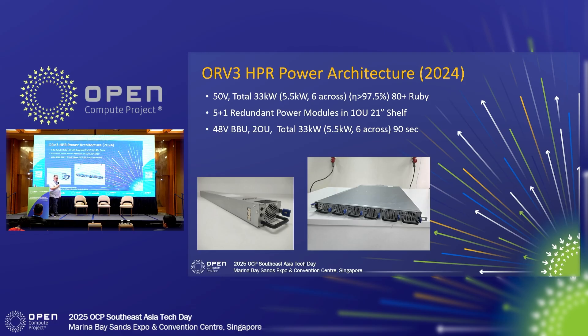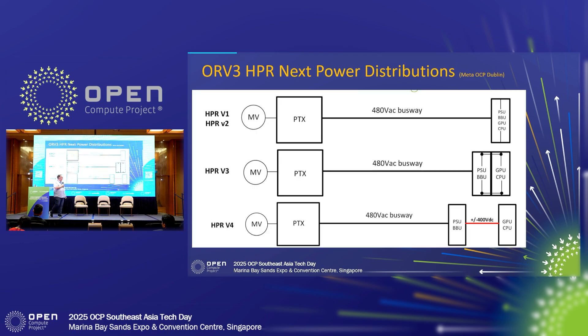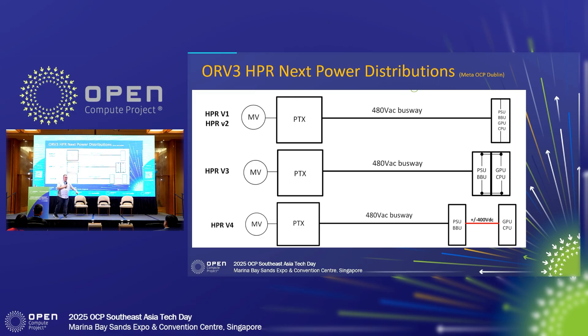What are we going to do next? Because 120 kilowatts is not enough. They're going to come out with the GB200 Ultra, which needs 130 kilowatts — I can just add another shelf for that. But beyond that they want 300 kilowatts in a rack. You heard about Mount Diablo in the earlier discussions. What they're going to do is take the power supplies and put them into a separate power rack — keeping all the compute in one rack and all the power in another — and connect them with bus bars. We're still at 50 volts for this.